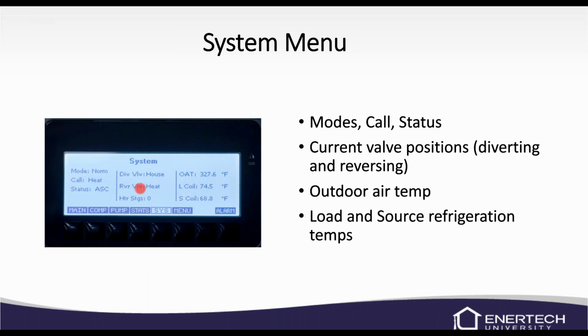System menu, it'll tell you what mode that it's in, whether that's a normal, emergency, auxiliary, whatever that may be. The current call, so your heating call. The status of the unit, this one happens to be an anti-short cycle right now, or ASC. It'll show you the diverting valve position, the reversing valve position, your heater stages, outdoor air temperature, which I would imagine this one's not plugged in or something because it's 327 degrees. It'll show what your load coil temperature is and your source coil temperature.